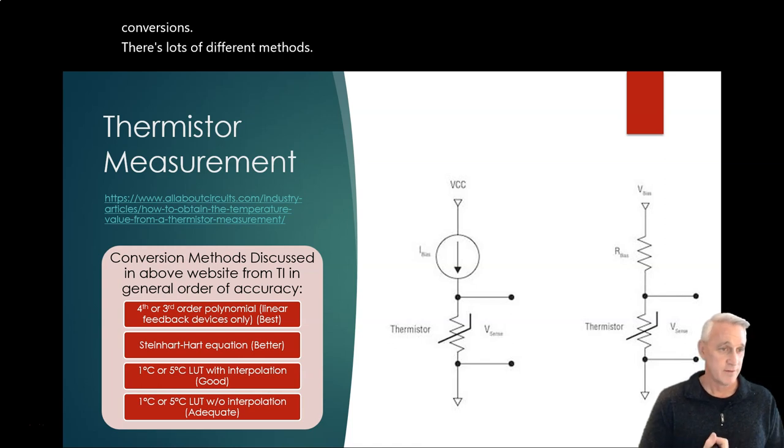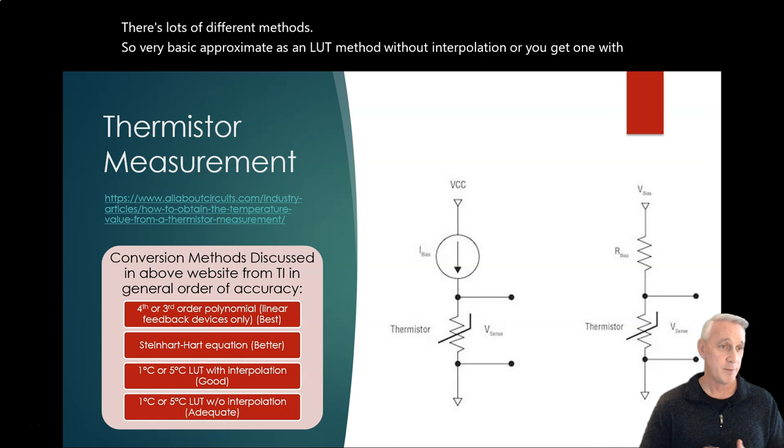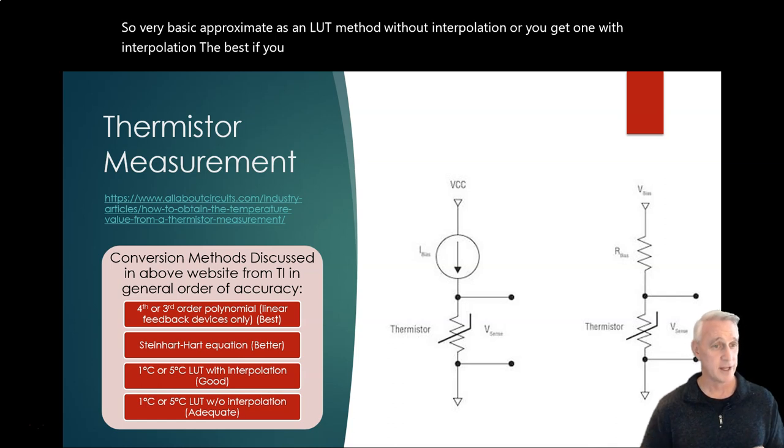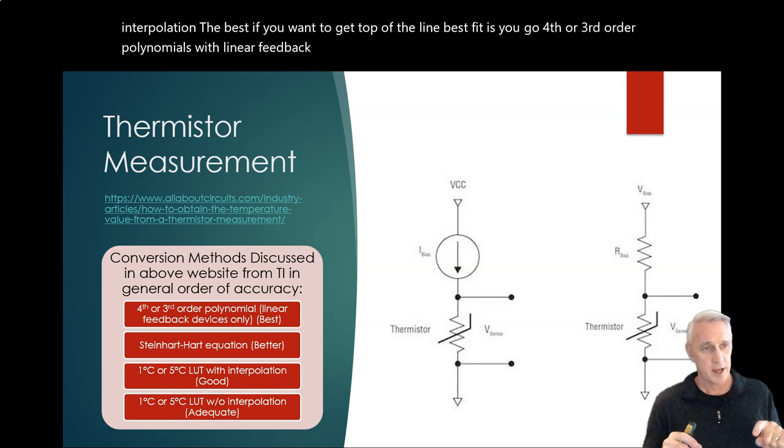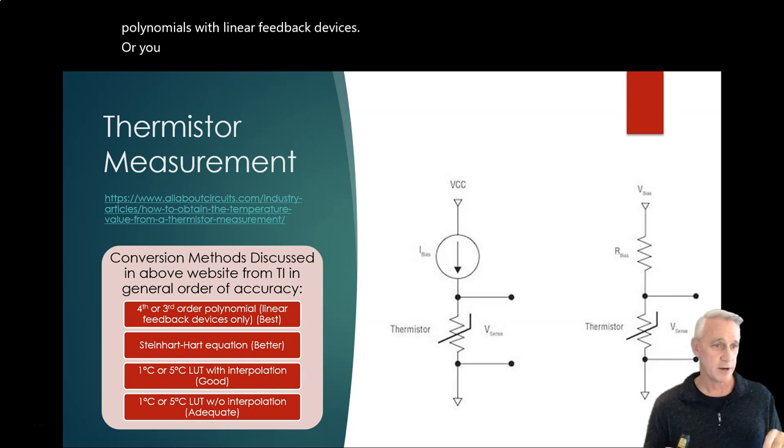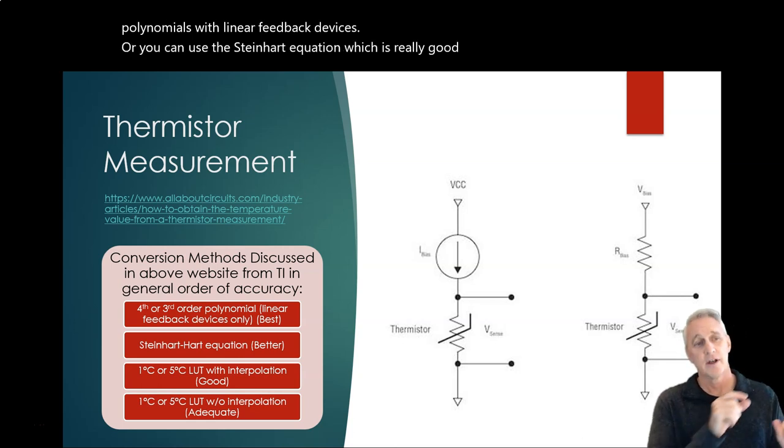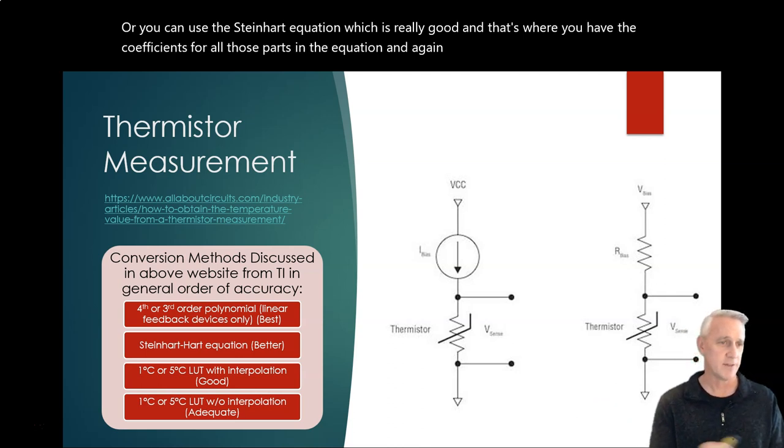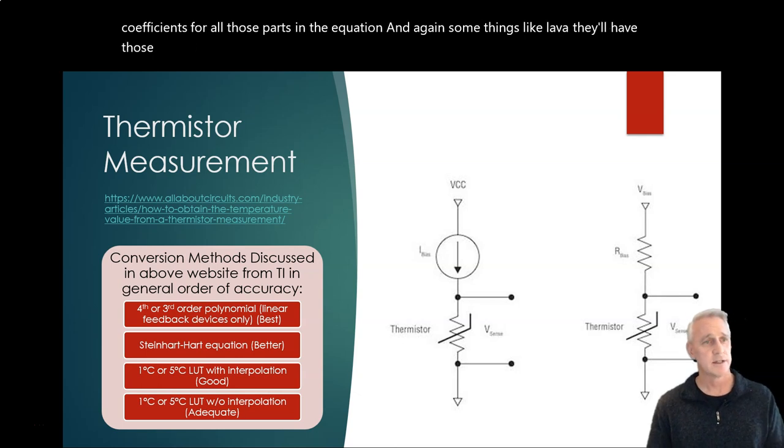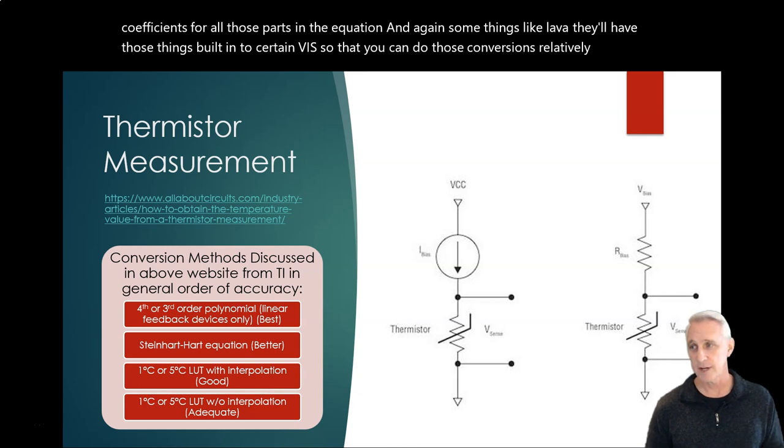Very basic approximate is an LUT method without interpolation, or you get one with interpolation. The best, if you want to get top of the line best fit, is you go fourth or third order polynomials with linear feedback devices. Or you can use the Steinhardt equation which is really good, and that's where you have the coefficients for all those parts in the equation. Like things like LabVIEW, they'll have those things built in to certain VIs so that you can do those conversions relatively easily and you don't have to reinvent the wheel with everything.